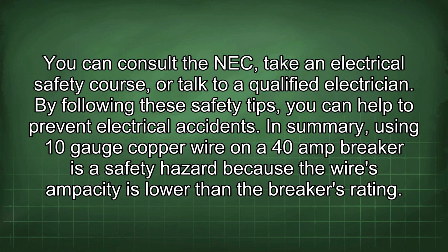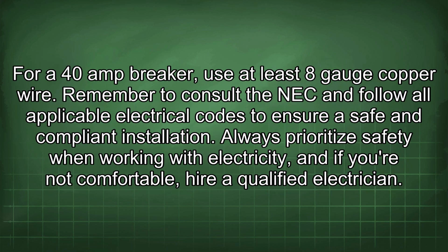In summary, using 10-gauge copper wire on a 40-amp breaker is a safety hazard because the wire's ampacity is lower than the breaker's rating. For a 40-amp breaker, use at least 8-gauge copper wire. Remember to consult the NEC and follow all applicable electrical codes to ensure a safe and compliant installation. Always prioritize safety when working with electricity, and if you're not comfortable, hire a qualified electrician.